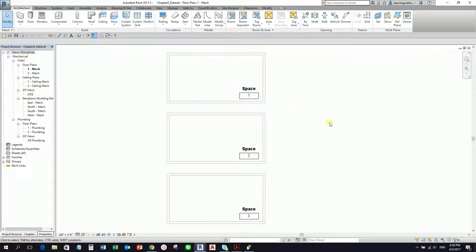Okay, by the way, why are the systems important? Like what I have said earlier, systems are the logical connection between elements in the model. So they are the link between the air terminal, the VAV box in HVAC, and the air handler, and they represent an additional layer of information above the physical connections made with ducts and pipes, known as the engineering information. So without these systems, ducts and pipes act only as connections between two points. Okay, so we need to create a system. So systems are needed to generate the bigger picture and allow us to manage the elements on a building-wide level.